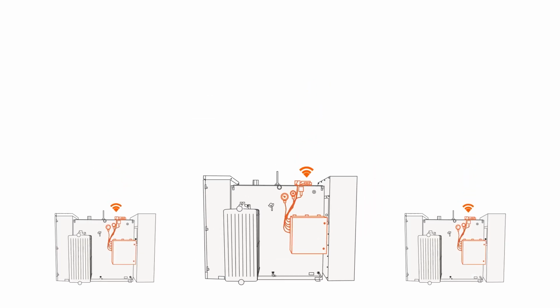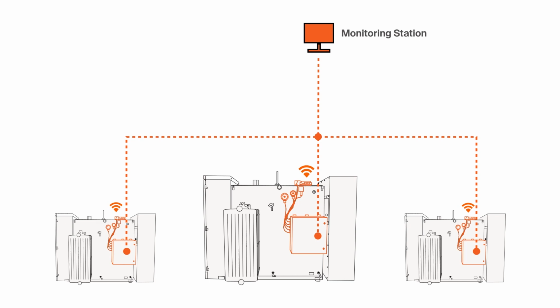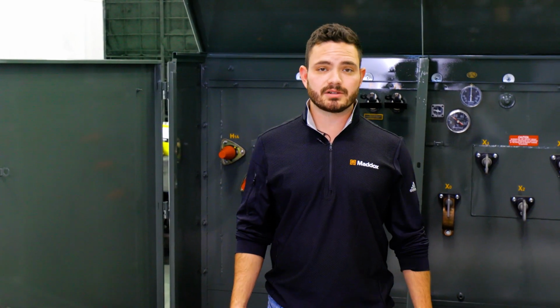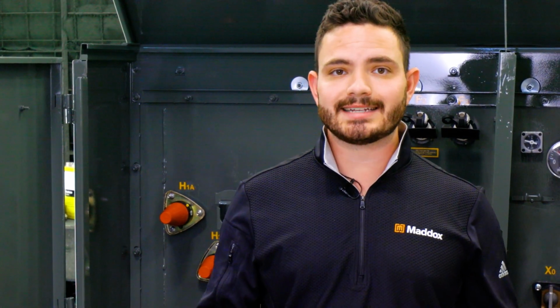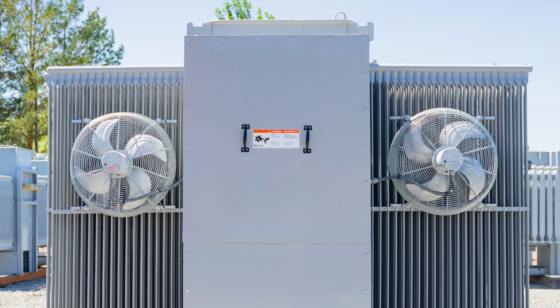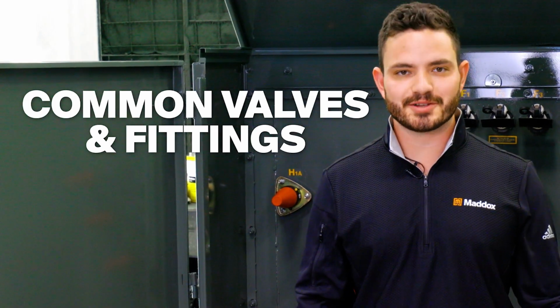These contacts allow companies to monitor their transformers from miles away, since the alerts can be sent to remote monitoring stations. Alarm contacts can also be used to activate fans on transformers. Much like the fan on your car's engine, transformers can use alarm contacts to automatically turn on fans during periods of peak loading and then turn them off as the transformer cools down. Last, let's look at some common valves and fittings on transformers.